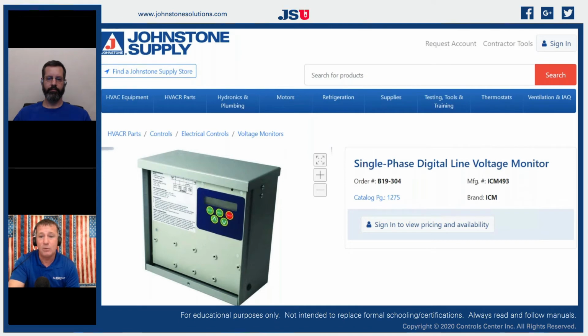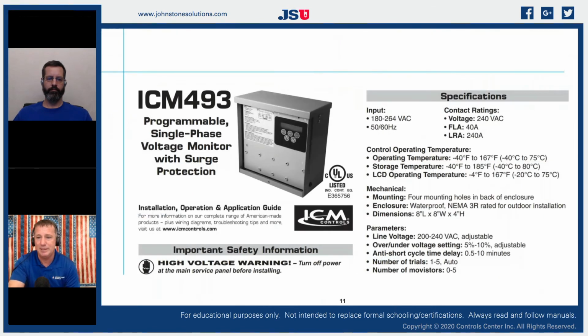So that's the ICM 493. We know it as the B19304. Just a superb piece of equipment. It's got an FLA rating of 40 amps, locked rotor at 240, and it has input capabilities from 180 up to 264. The one thing that I will say about some of these controls is electronics are temperature sensitive, and a lot of times our screens are temperature sensitive as well. So if you notice, the LCD operating range on that 493 is actually -4. So if you're servicing a heat pump in the middle of winter and it's below -4, you may not get a readout on the screen, because that actually will read the current voltage situation that you have and any kind of faults as well.